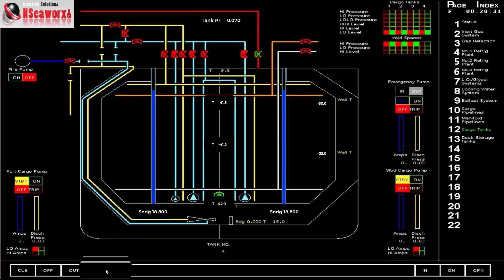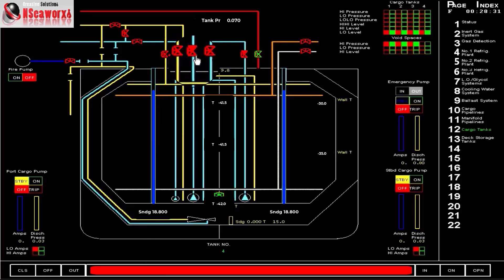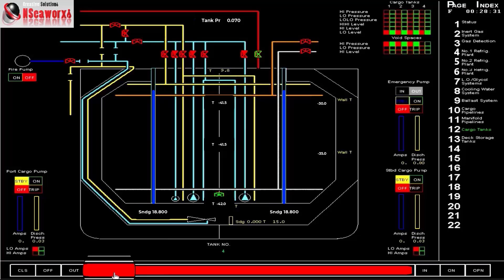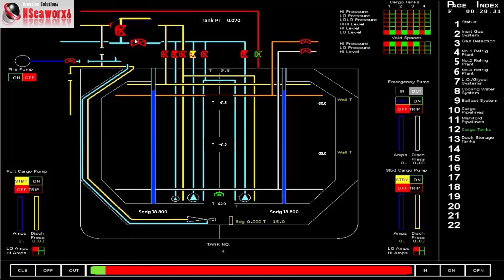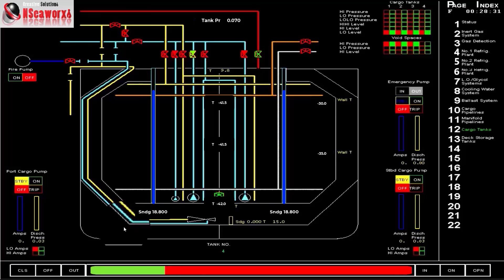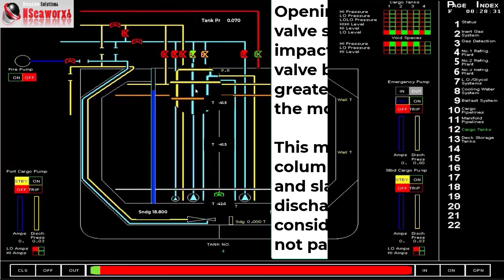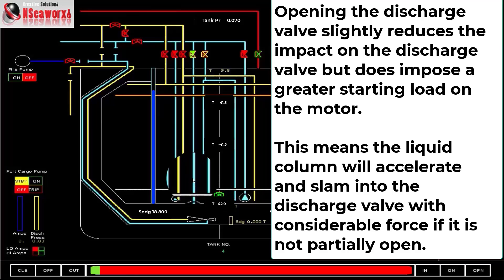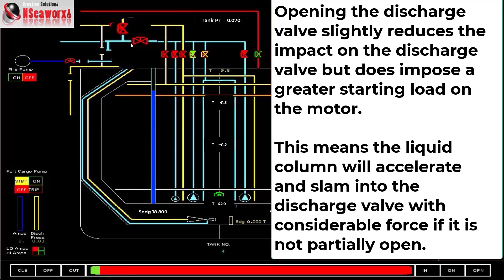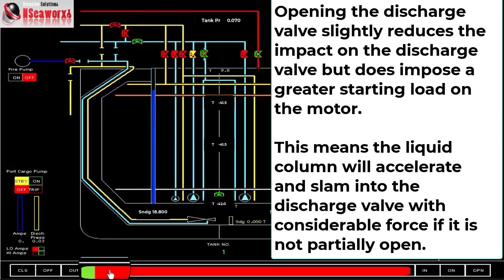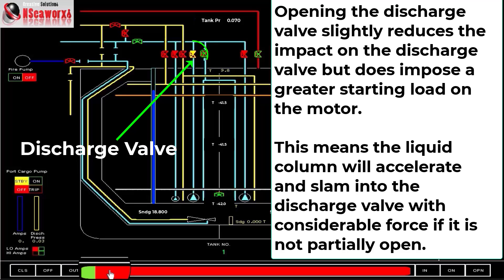So in practice we open a little bit the discharge valve crack open. And the other loading discharge line. And we only crack open a little bit the circulation line so that even if we start the pump, it just goes back to the liquid line. Now, cracking open the discharge valve is better. Unlike other centrifugal pumps, they can be closed even with the start of the pump. But with the deep well pumps, it is advisable. Check your manufacturer's maker anyway. That the discharge valve should be open because you have a height of a liquid column.